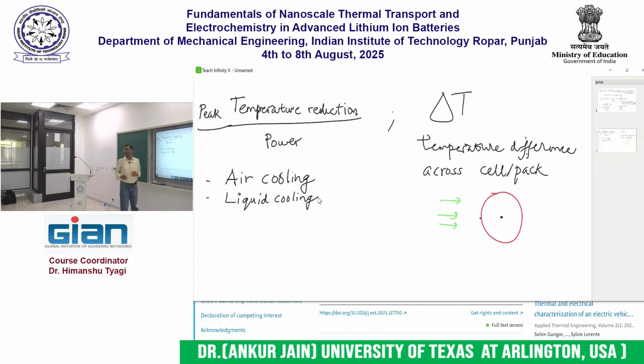Within liquid cooling, the most common coolant used is water. But a key disadvantage of water is that it cannot make direct contact with your cells. You can blow air over your cells, but you cannot blow water over them because the water will short your cells. So the cooling almost always has to be indirect — there has to be a thin sheet of something that separates the water from the battery pack you're trying to cool.